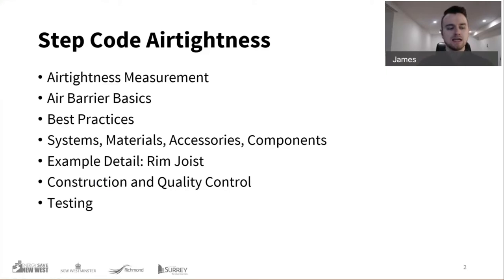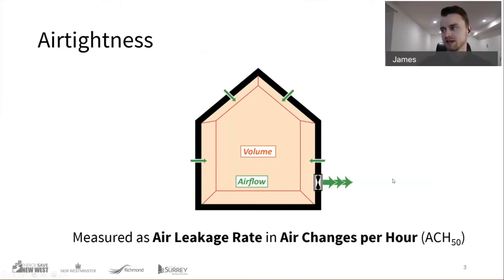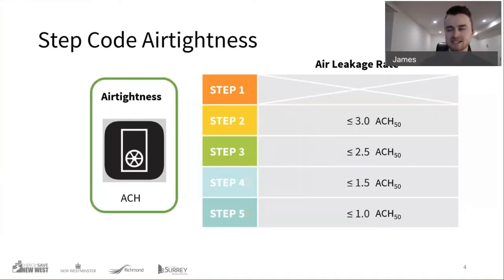In the context of a Part 9 building, we're dealing with a measurement known as ACH — air changes per hour. It's essentially a measurement of the volume of air that moves through the building during the test at a test pressure of 50 pascals — ACH50. Similar to golf, the lower the score the better. With the step code we have descending levels of air tightness: step 2, 3, 4, 5 — and hitting these targets plays a huge role in hitting the energy targets for each step.